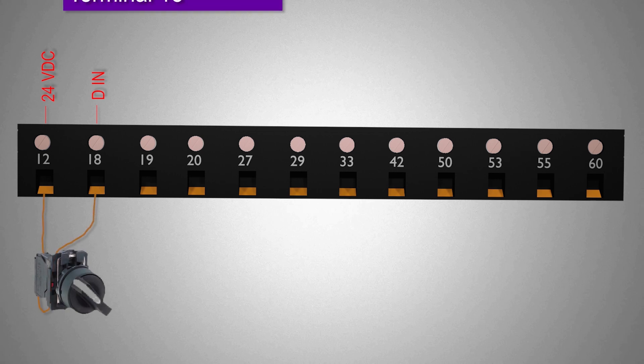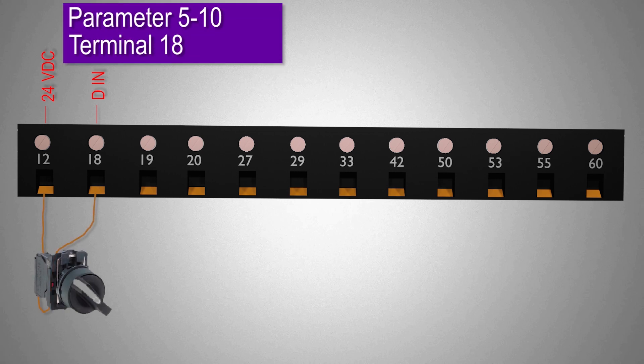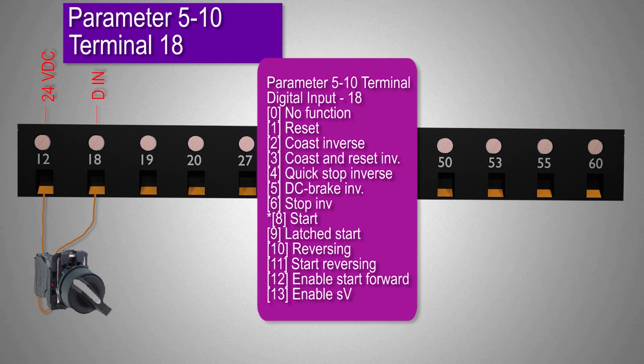The functions for terminal 18 can be programmed by using parameter menu 5-10. We can select a function for terminal 18 from the menu like start, stop, reverse and reset functions. For today's tutorial we will set 8 in parameter 5-10 to program this terminal as start signal input.